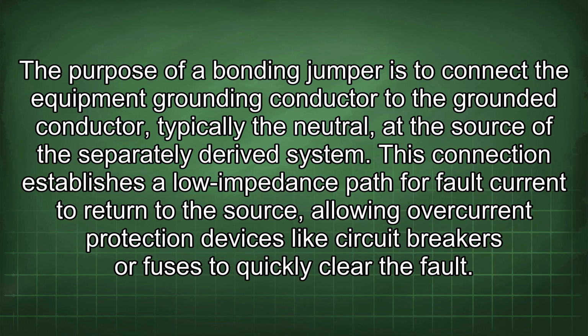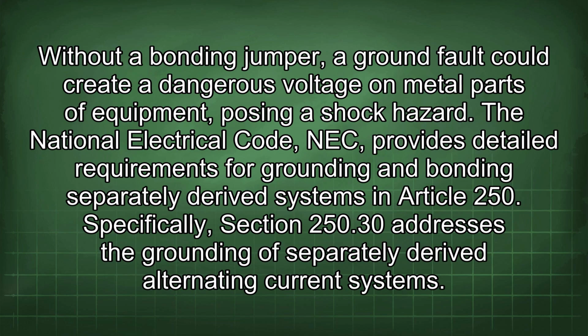This connection establishes a low impedance path for fault current to return to the source, allowing overcurrent protection devices like circuit breakers or fuses to quickly clear the fault. Without a bonding jumper, a ground fault could create a dangerous voltage on metal parts of equipment, posing a shock hazard. The National Electrical Code (NEC) provides detailed requirements for grounding and bonding separately derived systems in Article 250.